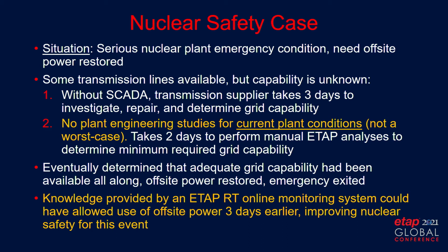It took 2 days to manually perform ETAP analyses to determine the minimum required grid capability for this situation. We eventually determined that adequate grid capability had been available all along, and offsite power was restored, and the emergency was exited.